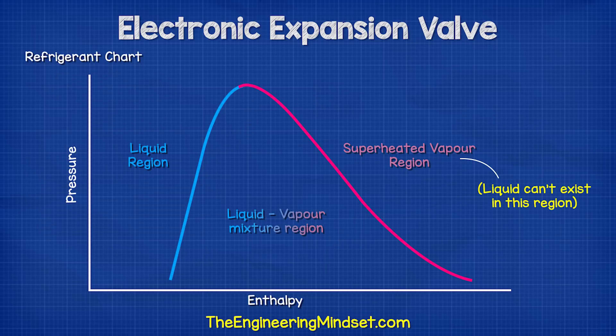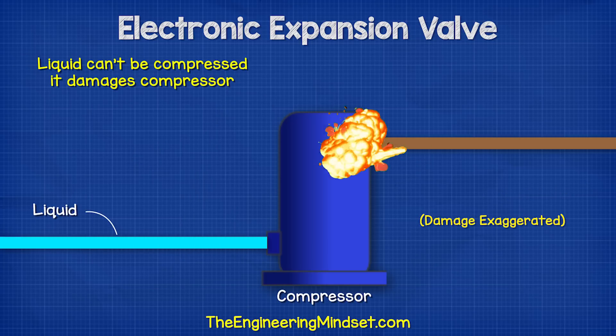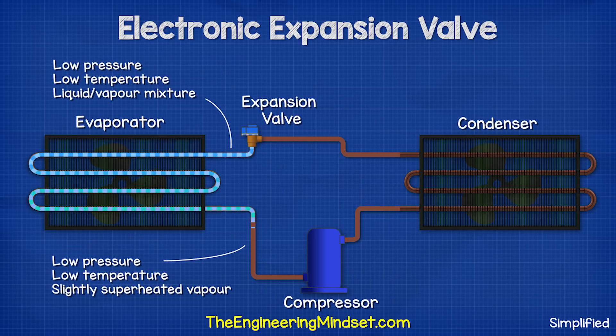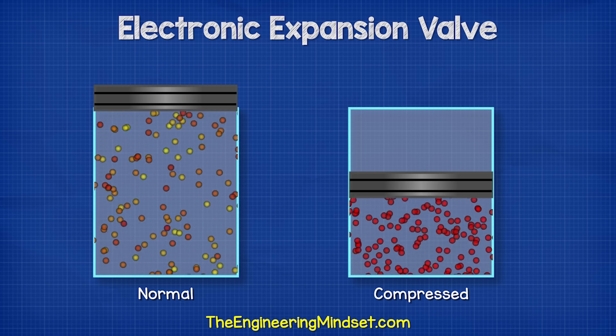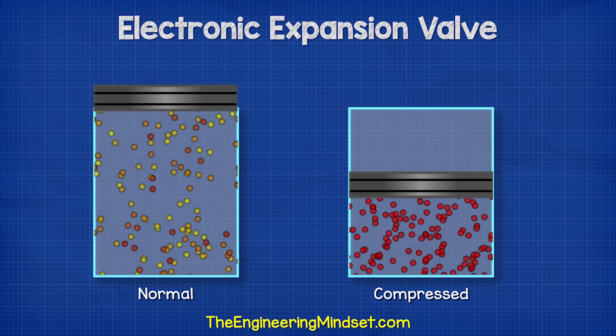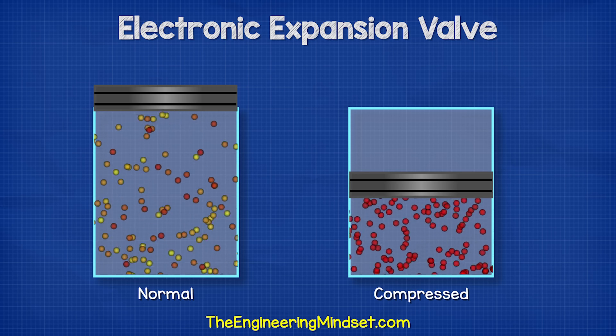Superheated basically means it's now completely gas and doesn't contain any droplets of liquid refrigerant. Liquid damages the compressor so we want to ensure it can't reach the compressor. The compressor sucks in the refrigerant leaving the evaporator as a low pressure, low temperature, slightly superheated vapor. It then squeezes this together into a much smaller space and so the pressure increases. All the heat which was picked up in the evaporator is now contained in a much smaller volume so the temperature will increase.